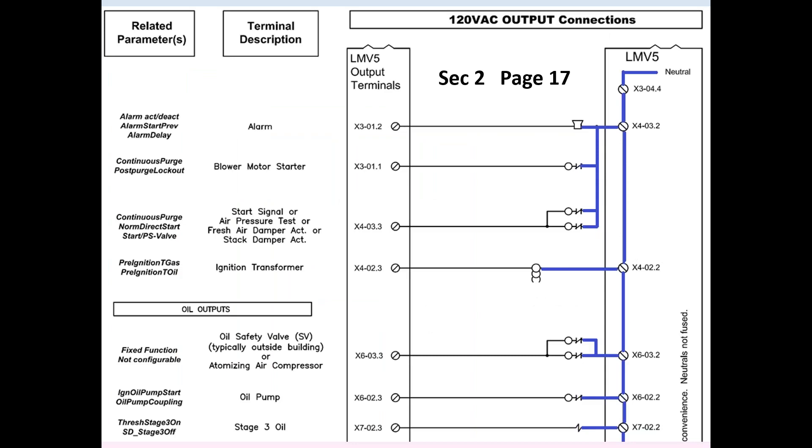This is followed by all the line voltage outputs of the LMV-5. Again, parameter, description, terminal. Notice to the right, shown in blue, all of the neutral terminals are connected to each other. The more discrete terminals you have for inputs and outputs, the more you can customize an LMV-5 for a specific application, and the better the diagnostic capability.